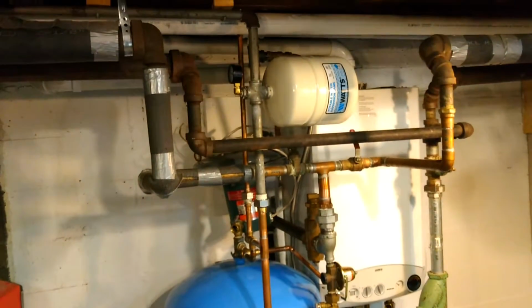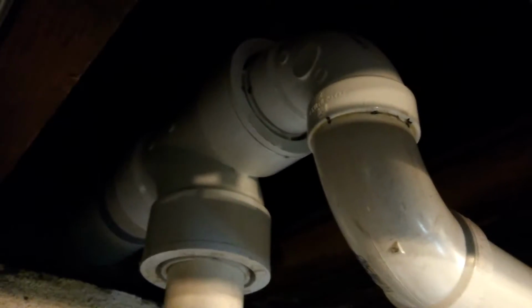But also the venting. The venting, they wanted like $500 something for a coaxial kit that comes all the way up and out. So I just made it out of PVC stuff that I could find at the restore. Just a T, bushing. I bored this bushing out, and I also have another T on the outside there. So I bored that bushing out on the inside and on the outside. So I have one solid length of 2-inch going all the way out for the exhaust, which is all solvent welded together.